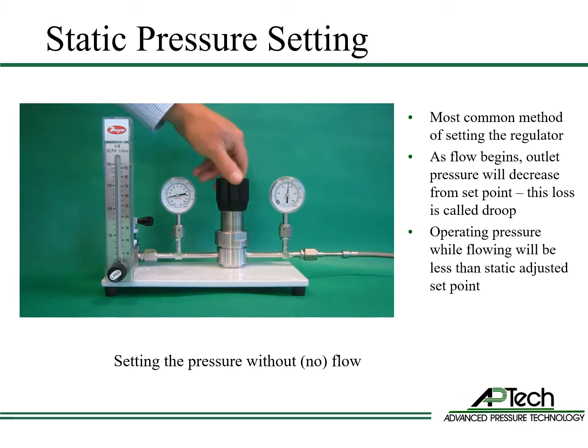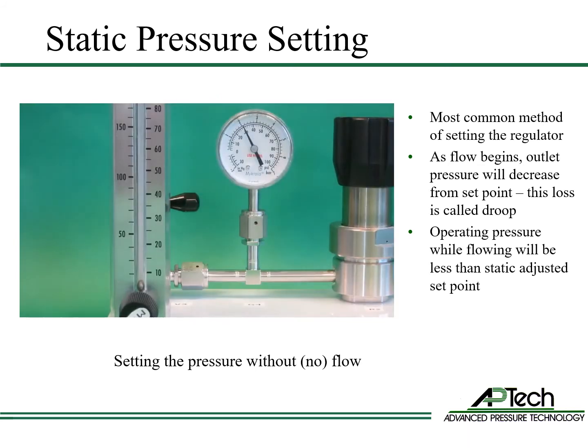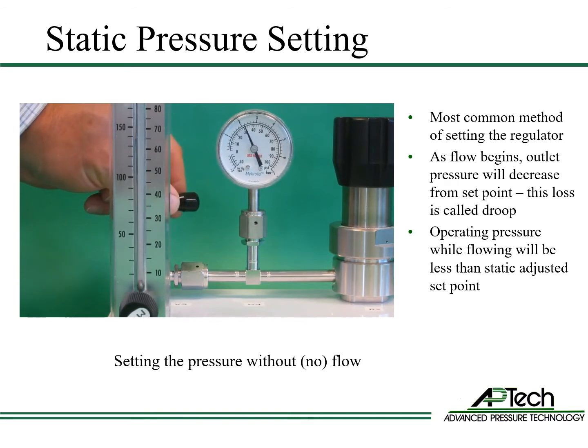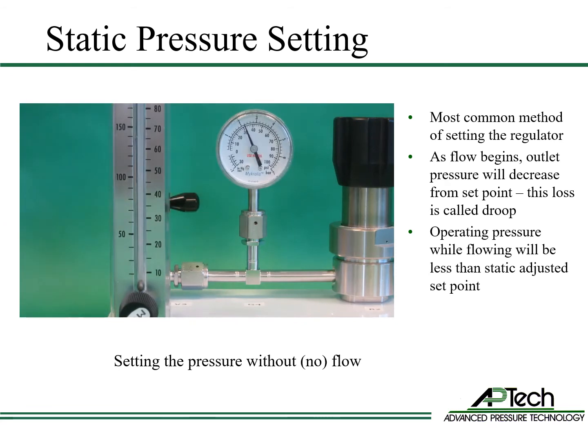Now we'll demonstrate two methods to set the outlet pressure. The most common method is static pressure setting, which means setting the pressure regulator with no flow. As flow begins, outlet pressure drops compared to the setpoint due to droop. When flow stops, the outlet pressure will rise slightly above setpoint due to creep or lockup. This is normal and will be explained in detail in later training.